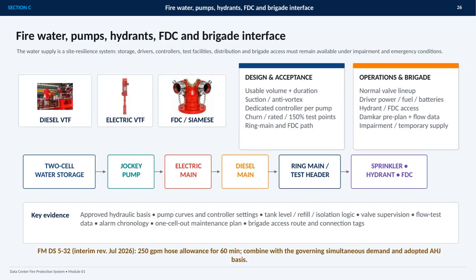This section focuses on the fire-water system and its connection to emergency response. The central idea is that water supply is a site resilience system, not simply a collection of pumps and tanks. Storage, drivers, controllers, testing arrangements, distribution, and brigade access all need to remain available during impairments and emergency conditions. The arrangement shown includes 2-cell water storage, jockey and main pumps, both electric and diesel, a ring main with test header and connections serving sprinklers, hydrants, and the FDC or Siamese connection.